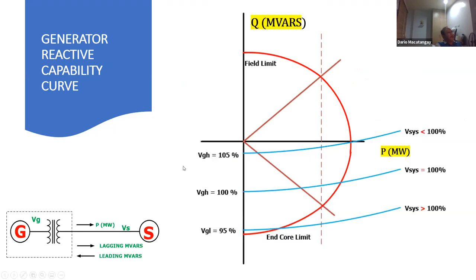Now, another effect is when the system is changing. At night the system voltage is high. So you're here, the system is high, so the generator needs to absorb more megavars. You can see here that the 95% line shifted to the very bottom here. You're getting to the end core limit here. Now, this is when the system is 100%, and this is when the system is operating at less than 100%. This is the voltage actually.